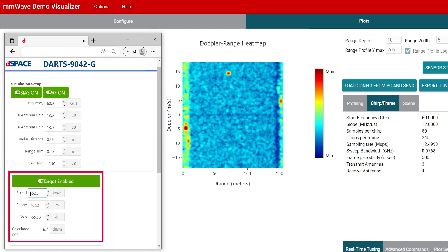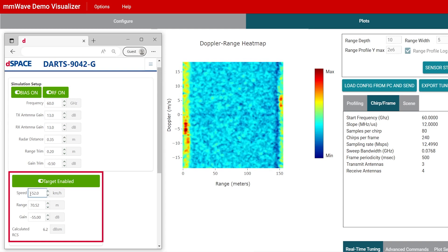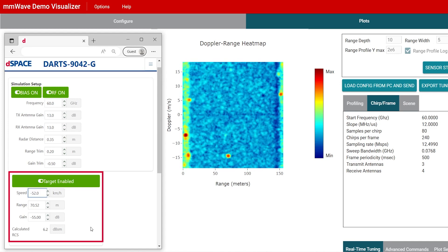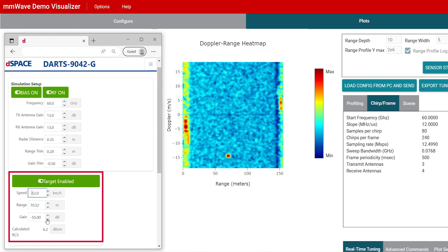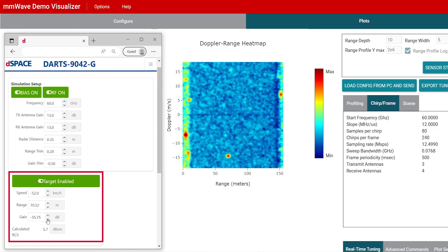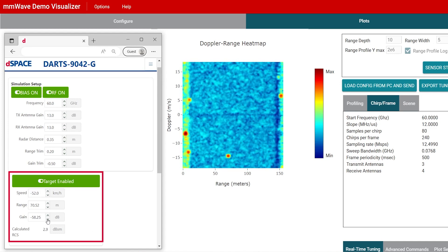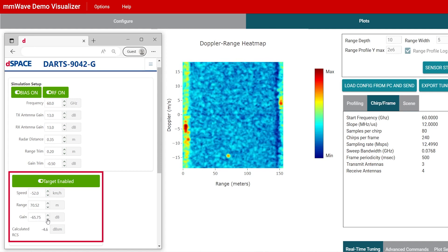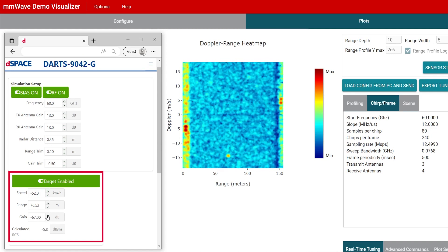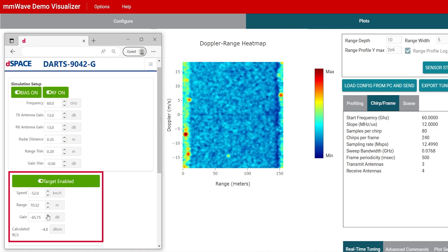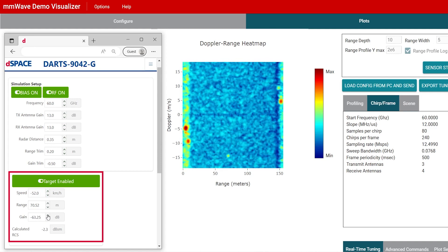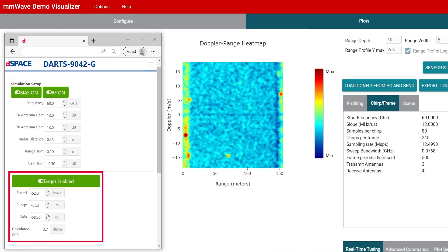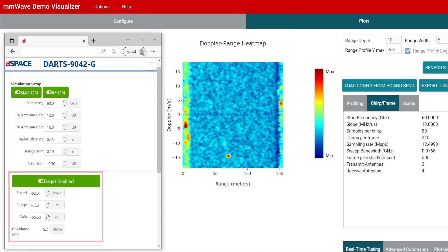With the last test parameter, also the radar cross-section of a target can be controlled. This kind of flexible reference target, which additionally has high reliability and repeatability, has become a standard tool to bring automotive radars to market in 24 and 77 GHz.